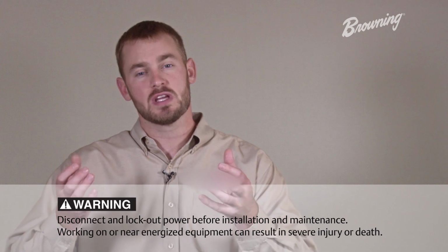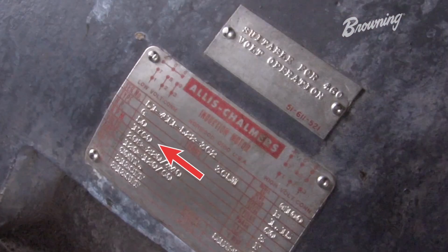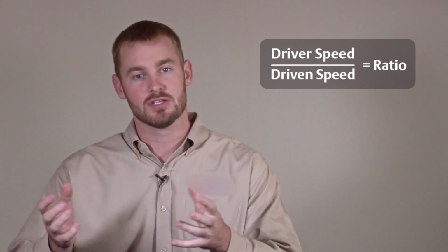One of the most critical aspects of drive retrofitting is to ensure that the new drive will operate very close to the same speed as the existing drive. In some cases, you may be able to retrieve the required driven or fan speed from a data plate or a test and balance label on the unit. If you cannot supply the required driven speed, it can be calculated using the motor nameplate speed and the mechanical ratio between the driver and driven sheave.